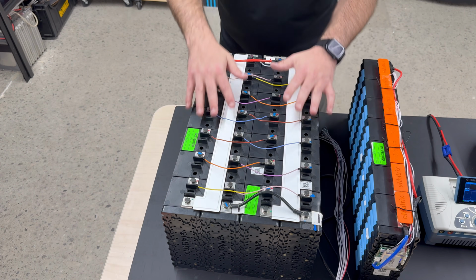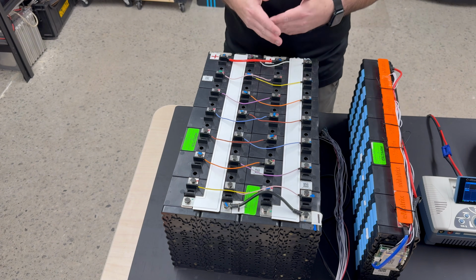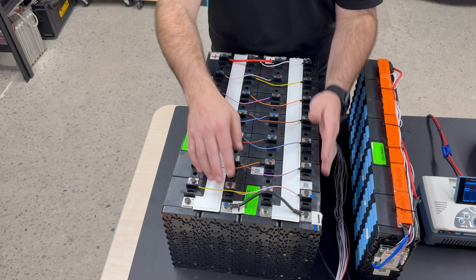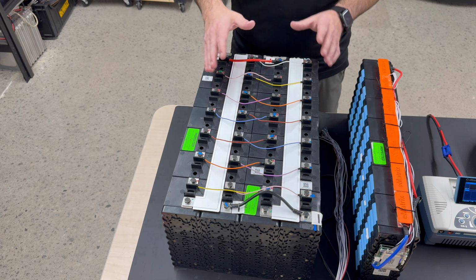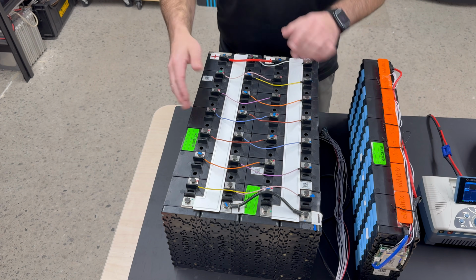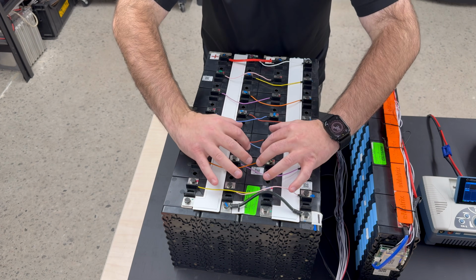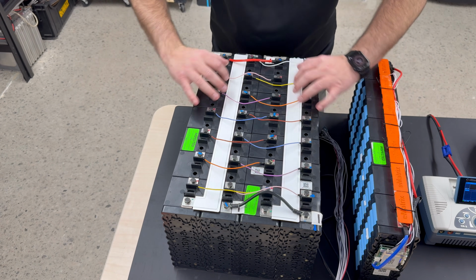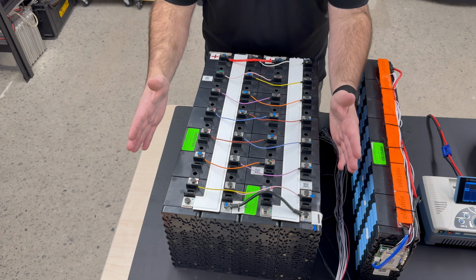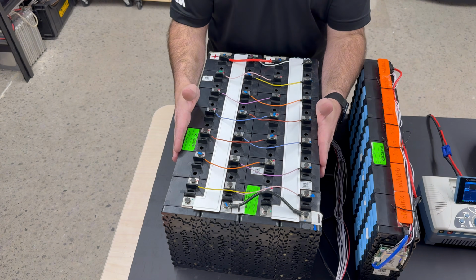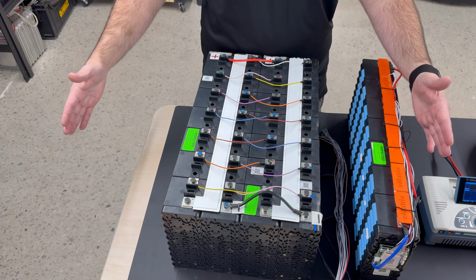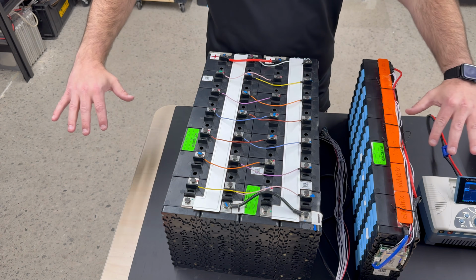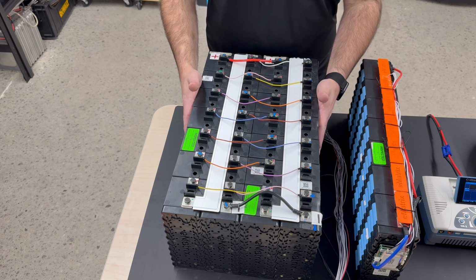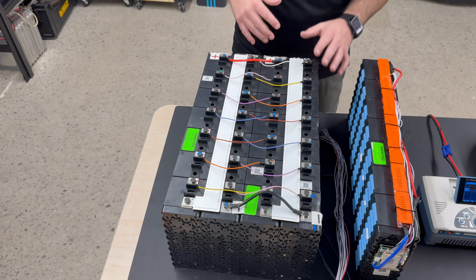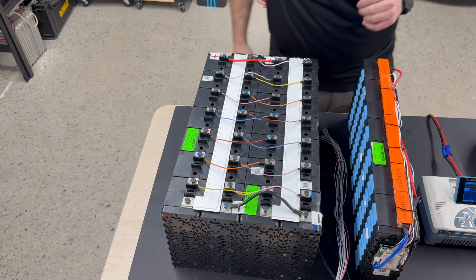So I'm going to go ahead and take all of these apart and then rewire it in the same configuration of a 2S 2P, but with the bus bar in the middle and then all of the paralleling wires on the sides. And then in that configuration, you could also add 6 or 8 modules, say, all into parallel, but staying at 48 volts. So let's go ahead and take this apart and rewire it in that configuration.